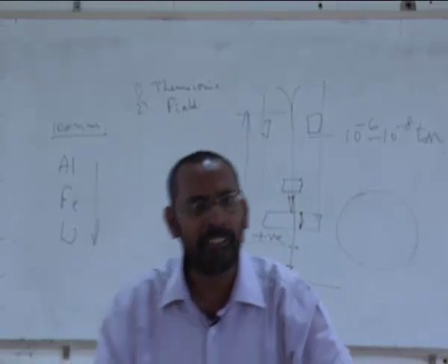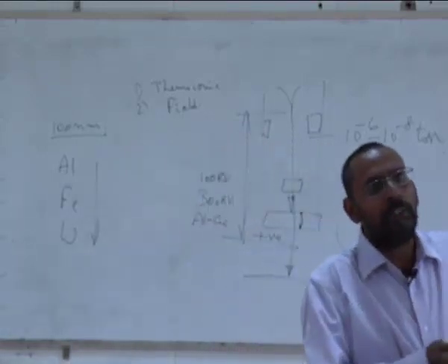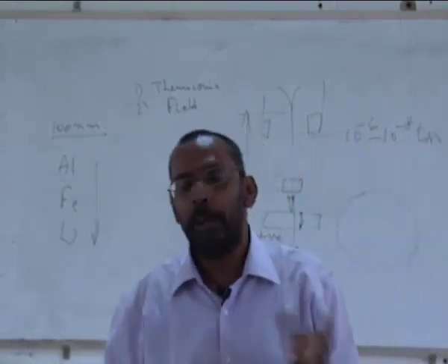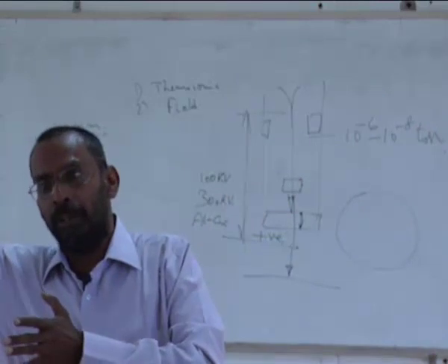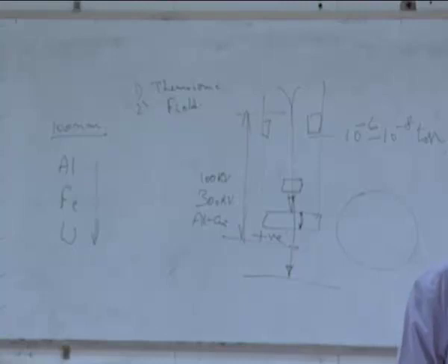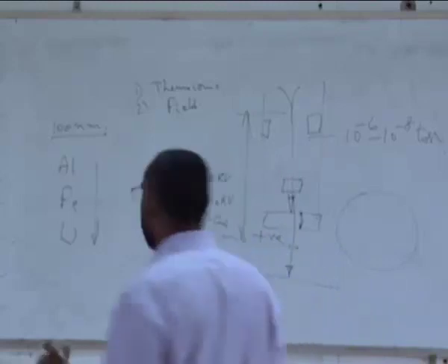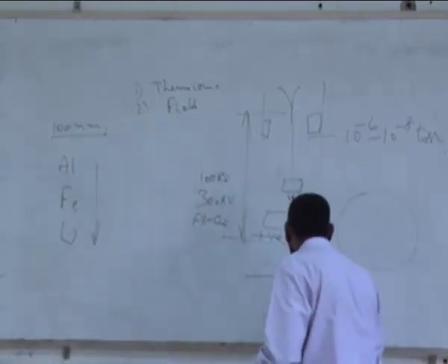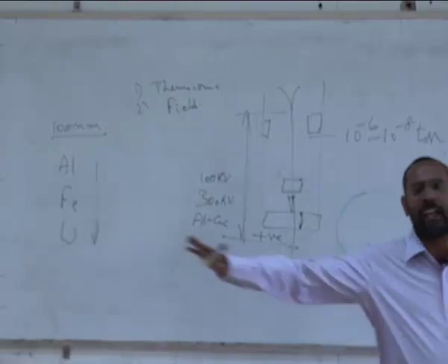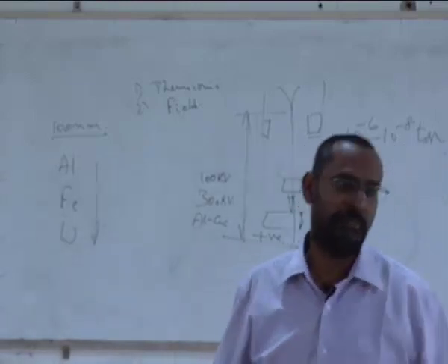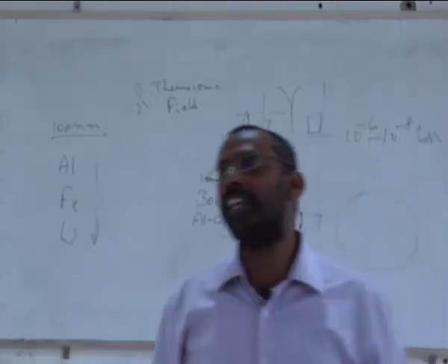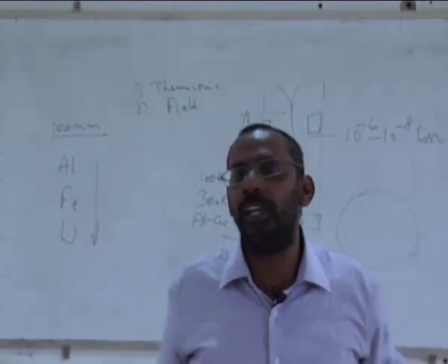Right? So as a result, if I am using very low atomic number samples, I can afford to have a thicker sample without losing the intensity of the beam. But if I am using a higher atomic number sample, if I am trying to look at the tungsten based alloys for some application, I need to use a very thin sample so that I don't lose the beam. What happens if I lose the beam? You will see that when I see the image here, the image looks completely black, dark, no contrast will be seen. So as a result, the beam that is coming out does not have any intensity at all, and you see everything as very dark.